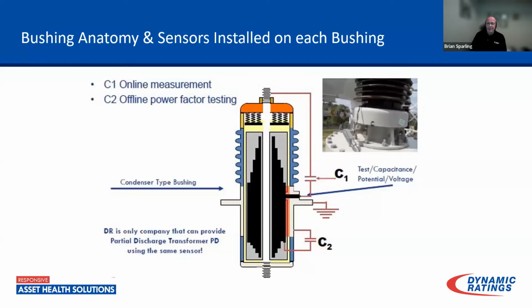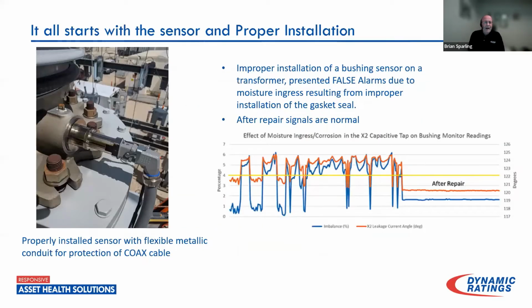On the right-hand side, you can see the bushing with the sensor installed on the tap, and it all starts with the sensor and a proper installation. On the left-hand side, you see the bushing sensor installed with flexible metallic conduit for protection of the coax cable running from the sensor down below to the monitoring system.